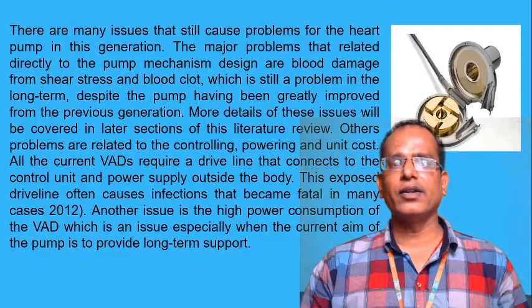All the current pumps require a driveline that connects to the control unit and power supply outside the body. This exposed driveline often causes infections that become fatal in many cases. Another issue is the high power consumption of these pumps, which is an issue especially when the current aim of the pump is to provide long-term support.